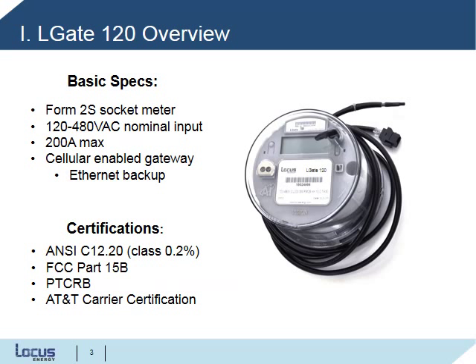To start things off, here are the basic specs for the LGate 120 meter. This is a Form 2S socket meter for single-phase PV monitoring. It's rated 120 to 480 volts AC nominal input and 200 amps max. The LGate 120 is a cellular-enabled gateway with Ethernet backup.